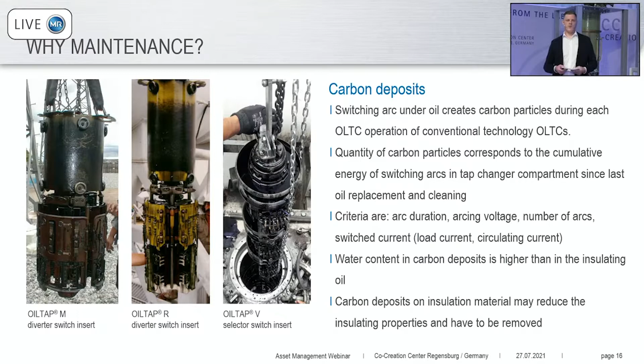Here are 3 example photos from left to right. This is the OILTAP M, OILTAP R and OILTAP V. Don't get shocked from that black color. This is a totally normal occurrence in conventional technology. However, if the parts are not regularly checked and cleaned in combination with high water, this can form or can reduce the insulating distance, and at the end of the day can form a creepage path where we then have a flashover inside the OLTC or on the insulating cylinder, for example, which then leads to a failure or outage of your transformer tap changer.